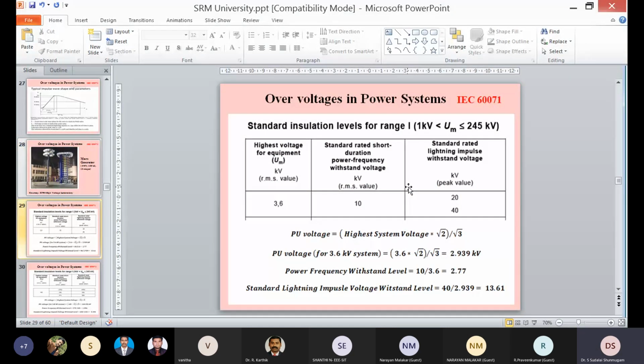So I am showing the calculation for a 3.6 kV system. If you have a calculator, kindly work along with me. It will help both of us. This is the table I have taken from IEC 60071. They have given three values here: the highest voltage for the equipment in terms of RMS value, the standard rated short duration power frequency withstand voltage in terms of RMS value, and the standard rated lightning impulse withstand voltage in terms of peak.